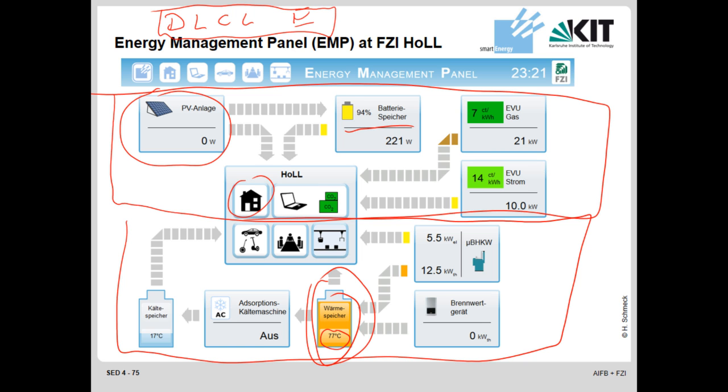And they went into the menus and could see how the temperature curves had developed, could immediately say which sensors had strange behavior, and then call the service company and tell them exactly what kind of situation is observable here. And they could immediately see, okay, that's the fault, we come and repair it.